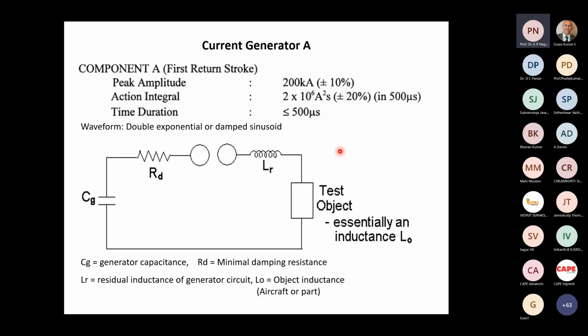The action integral is known as the integral of I squared dt. For a non-uniform current wave shape, I squared R is the instantaneous power, so the energy loss is I squared R dt in a small interval. The total energy is the integral of I squared R dt over the entire time. Since we cannot always define R in the test object, the action integral, the integral of I squared dt, is defined instead. In this case it is 2 times 10 to the 6 ampere squared seconds.